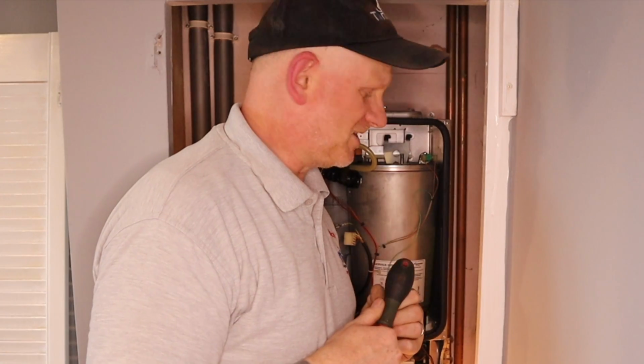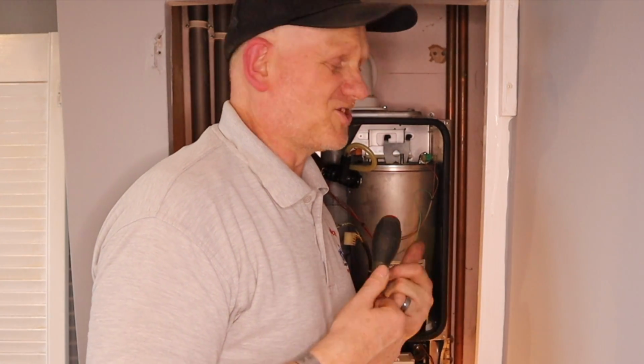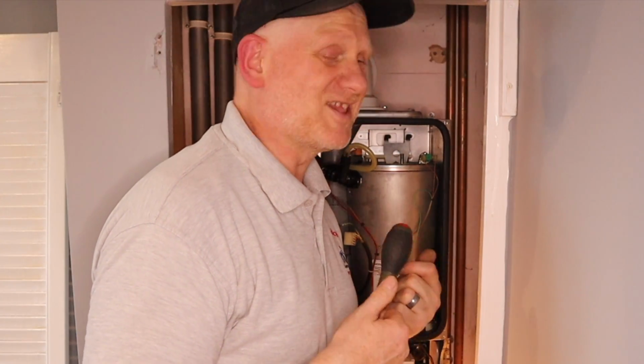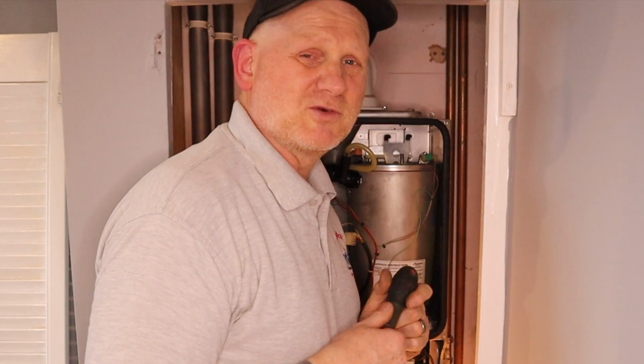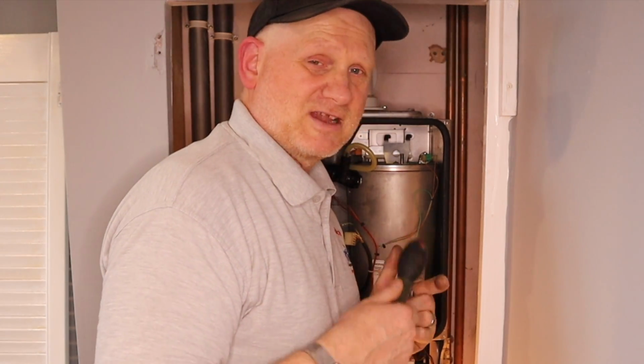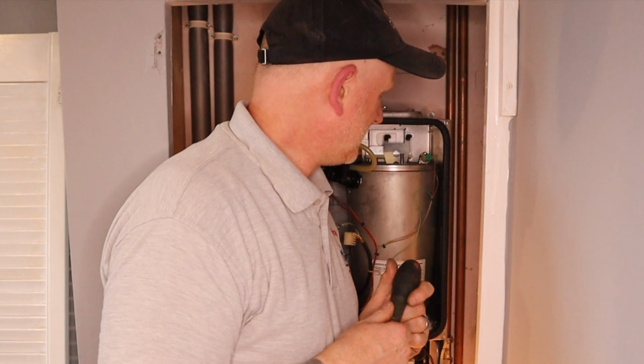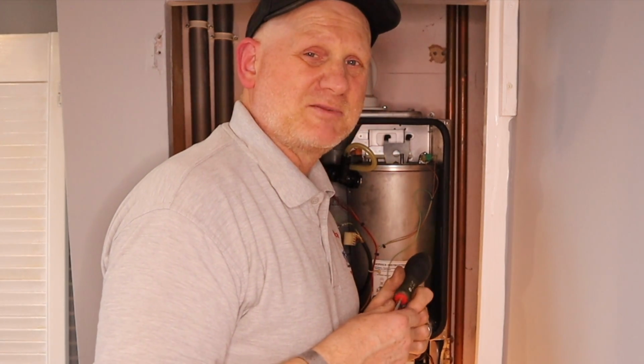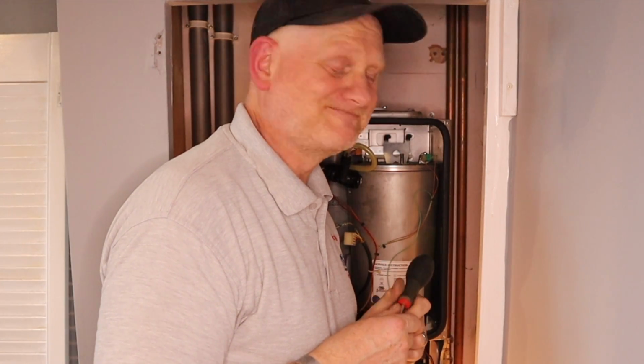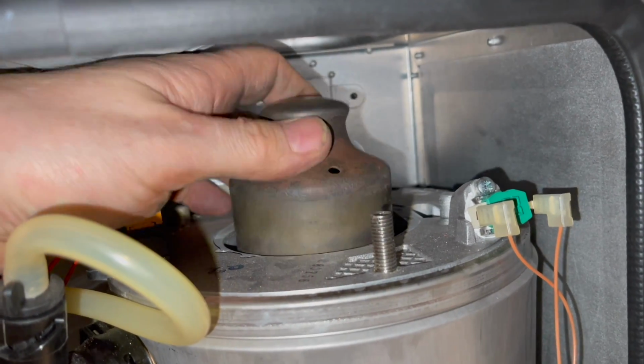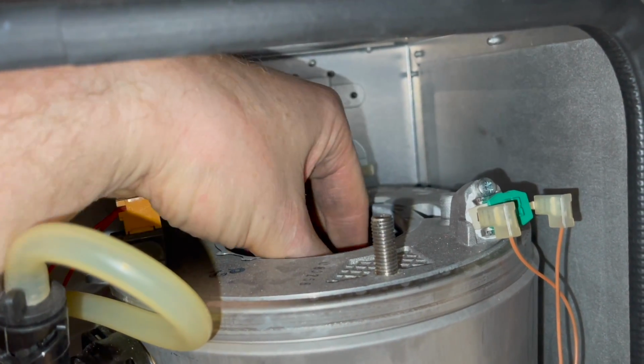And I knew, because this is LPG, because it's a lot hotter, and aluminium heat exchangers are not very good with LPG because it is so much hotter, I just knew it won't come out. Anyway, I'm going to have to put it back together again because we need some hot water for tonight, and then have plan B, which will probably be a new boiler. So the baffle's looking a lot cleaner, so I can put that in at least.